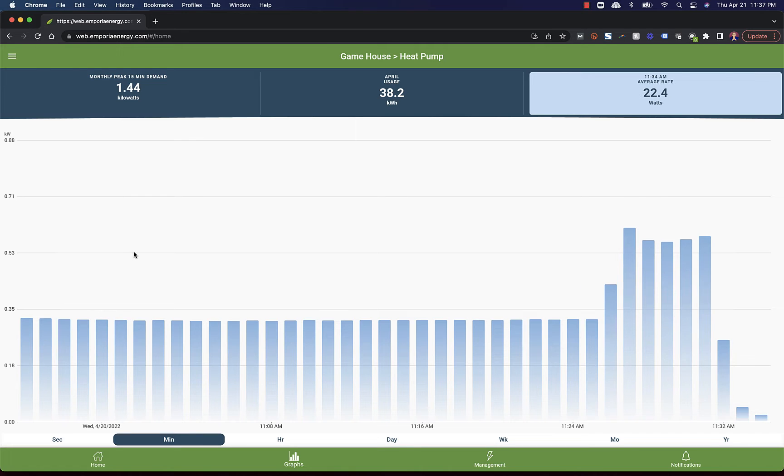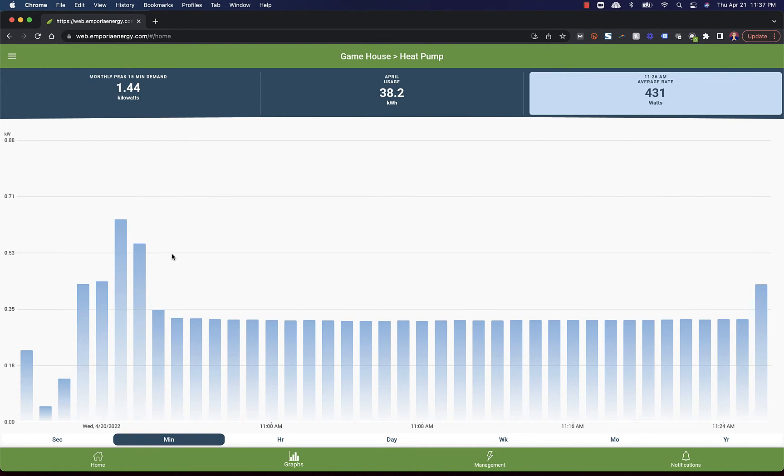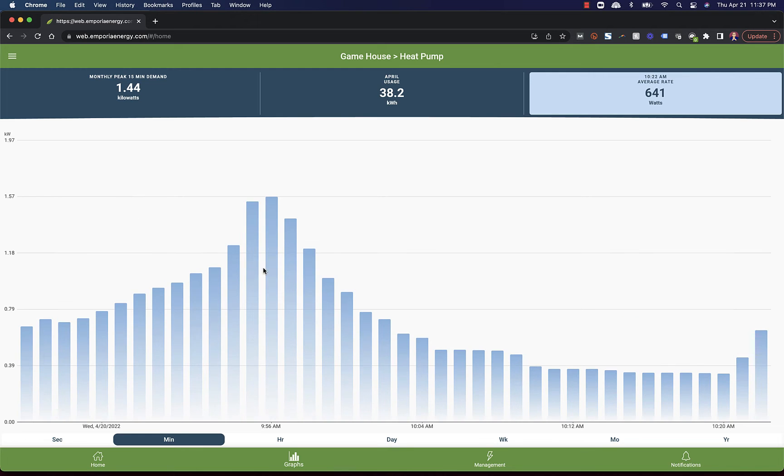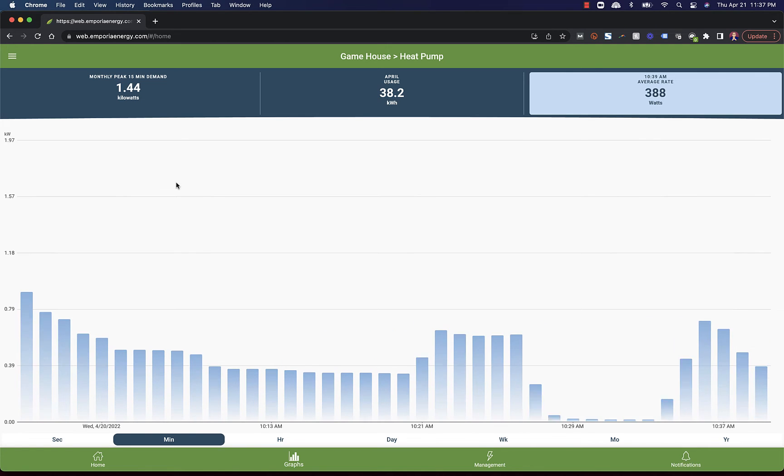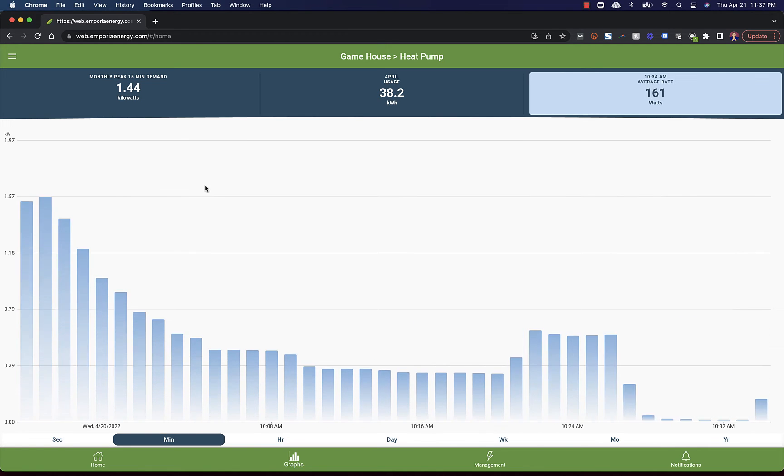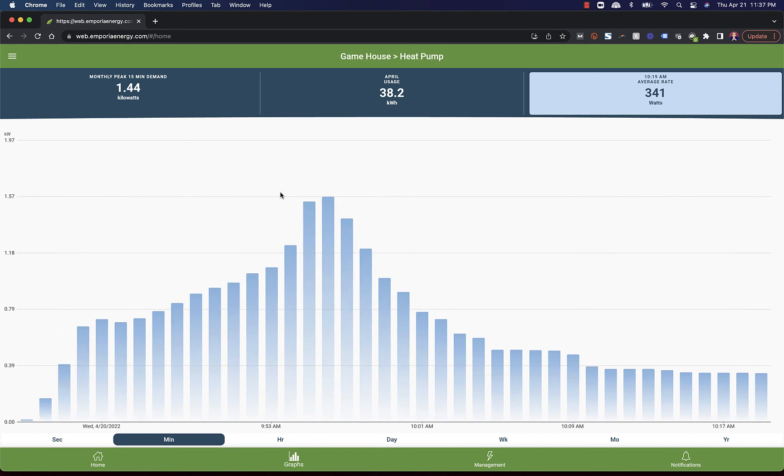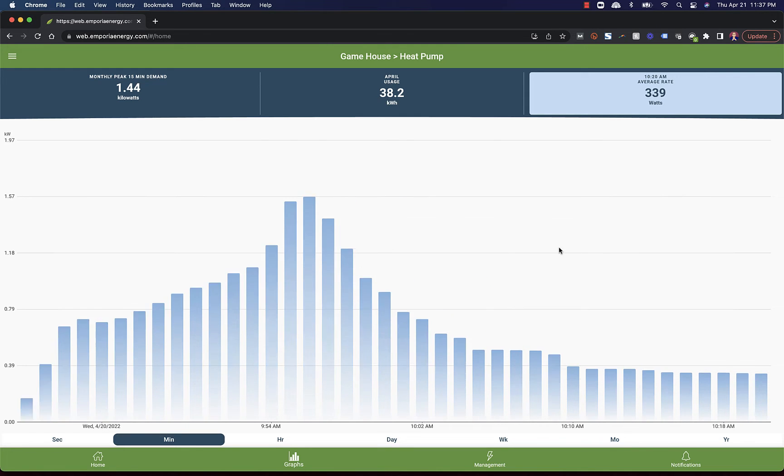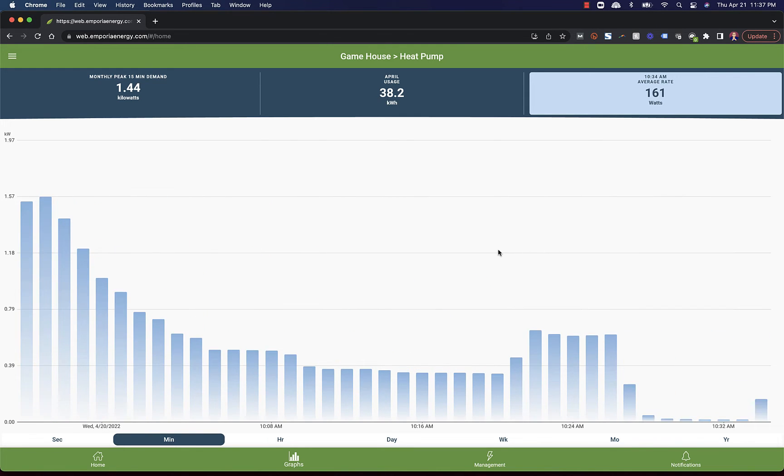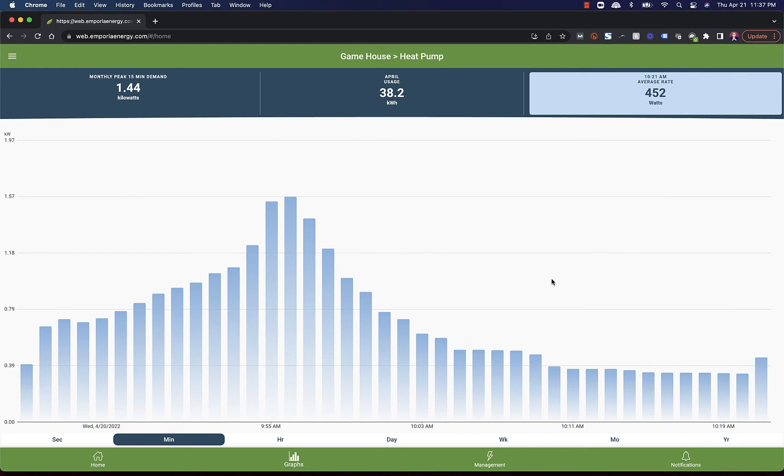But that's a nice long run cycle. And then it was only off for a little while. And then before that, it was on for a while too. Now this was the same thing. I probably turned the temperature up. So it ramped up to 1,600 watts or thereabouts and did a nice long run cycle. But this is what you want to see, I guess, is the point that I need to make. You want to see a system that ramps up relatively slow and then it runs low and slow for a long time. You want it to run as close to 24-7 as is possible. And I like seeing what I'm seeing out of the system.